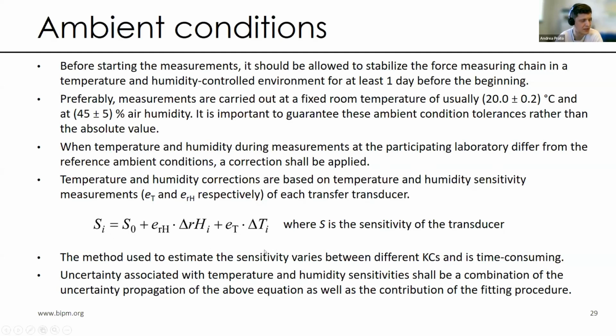As we can see, this is the formula that is usually used to correct the sensitivity of our transfer standards as a function of humidity and temperature. So these RH and ET are the sensitivity coefficients for humidity and temperature. There are different ways to measure these sensitivities, and these measurements are usually time-consuming, but they are fundamental in order to perform this kind of corrections. Also, uncertainty is associated with these sensitivities, basically given by the combination of the uncertainties of the single values from this formula, as well as the uncertainty contribution due to the fitting procedure.